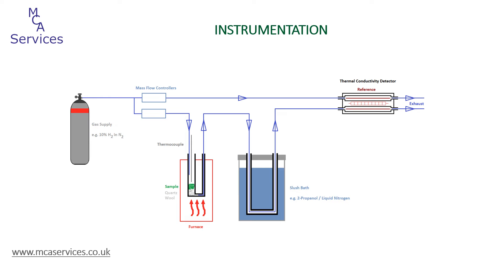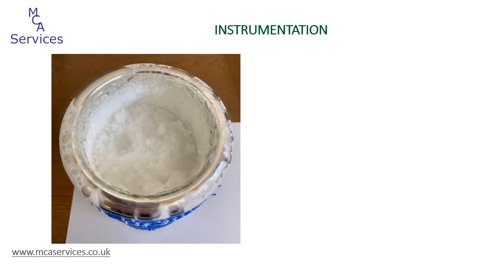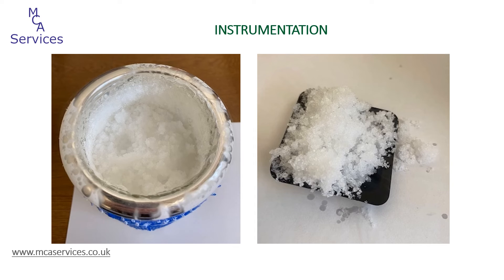In this case, we're passing the output stream through a cold trap before it reaches the TCD. The cold trap is formed from a slush bath, and for the removal of water we favour the use of liquid nitrogen and 2-propanol. This achieves a temperature close to minus 100 degrees C and it will easily last for the duration of a couple of analyses. This picture shows a propanol/liquid nitrogen slush bath in a Dewar that will be installed onto the instrument. It's a nice fine slush bath with no free liquid nitrogen, which means installing it over the cold trap should be reasonably easy, it's already stable, and it will easily last for three to four hours.